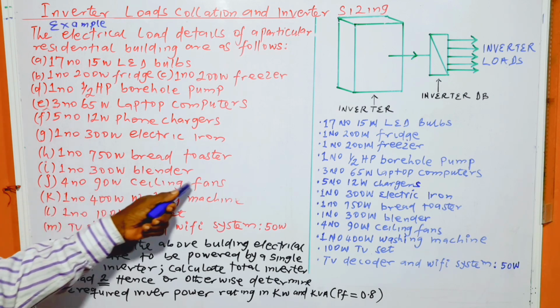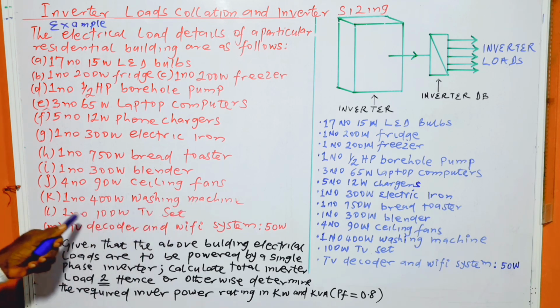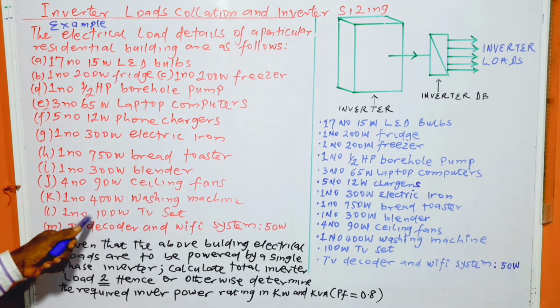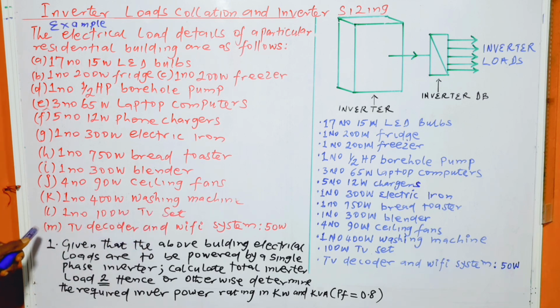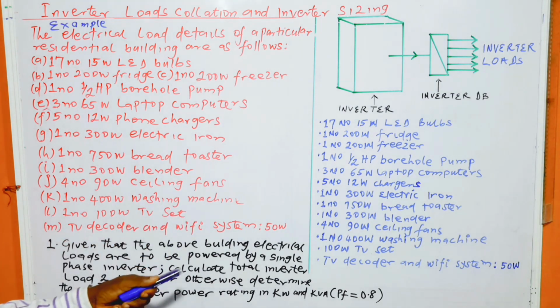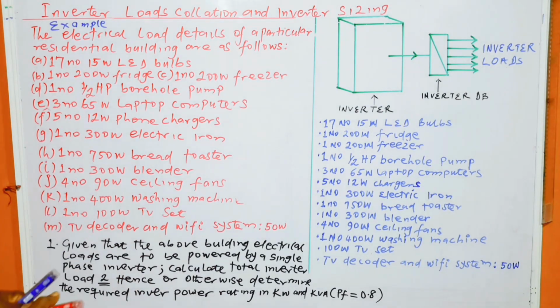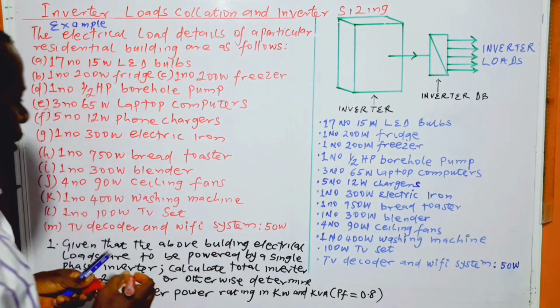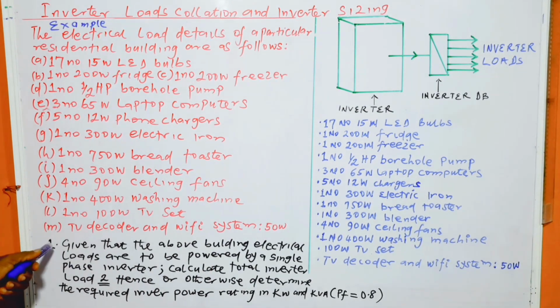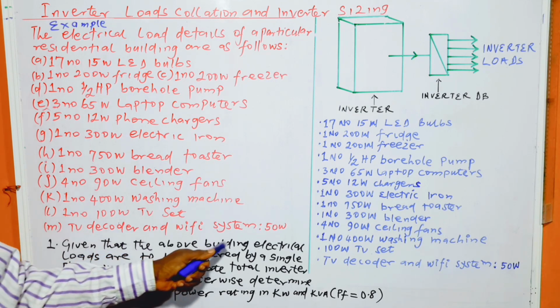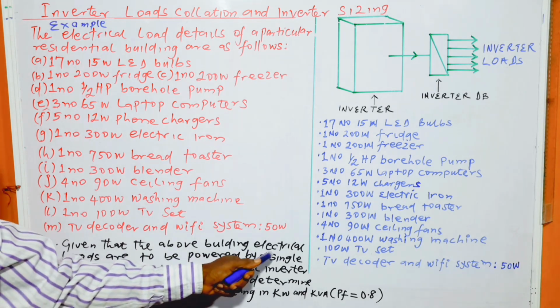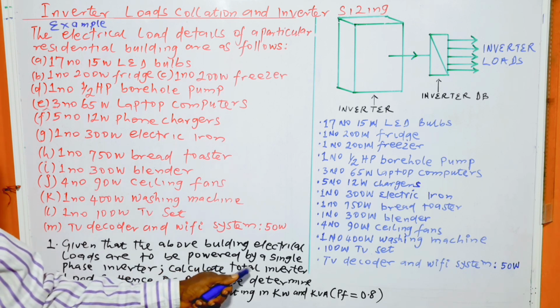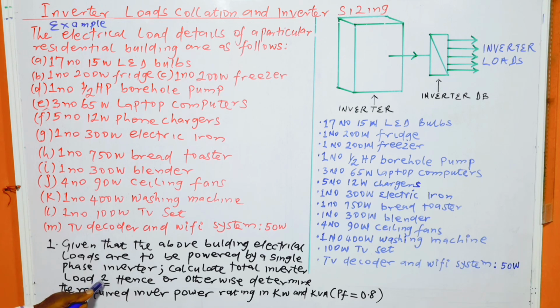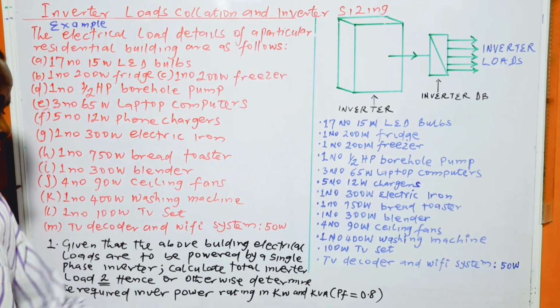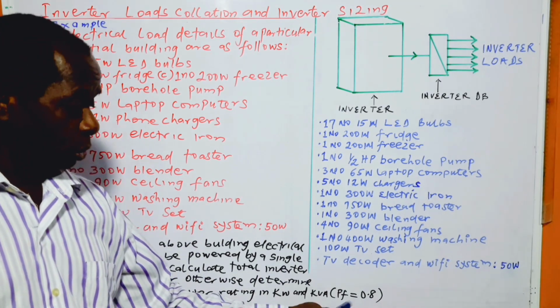J. Four number 90 watt ceiling fans. K. One number 400 watt washing machine. L. One number 100 watt TV set. M. TV decoder and Wi-Fi system, 50 watts. That is the power requirement for the decoder. So this is a washing machine. Now we move on. Given that the above building electrical loads are to be powered by a single phase inverter, one, calculate the total inverter load. Two, hence or otherwise determine the required inverter power rating in kilowatts and kVA. Take power factor to be 0.8.